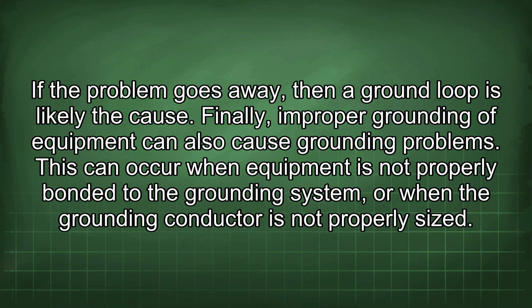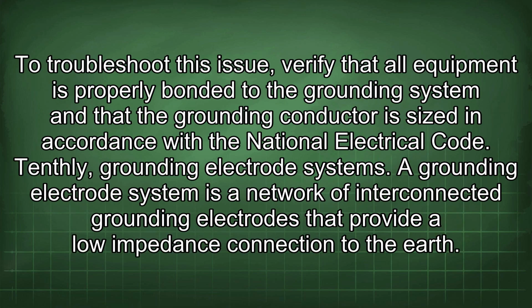Finally, improper grounding of equipment can also cause grounding problems. This can occur when equipment is not properly bonded to the grounding system or when the grounding conductor is not properly sized. To troubleshoot this issue, verify that all equipment is properly bonded to the grounding system and that the grounding conductor is sized in accordance with the National Electrical Code.